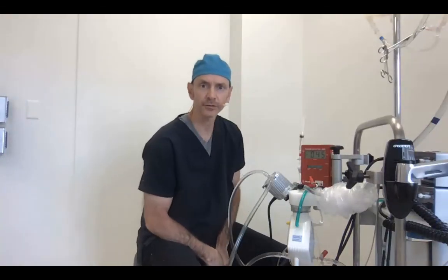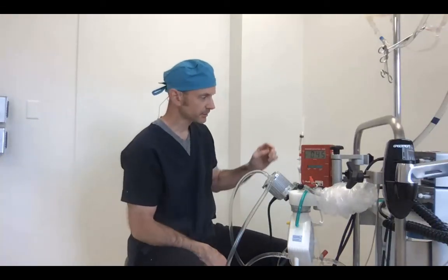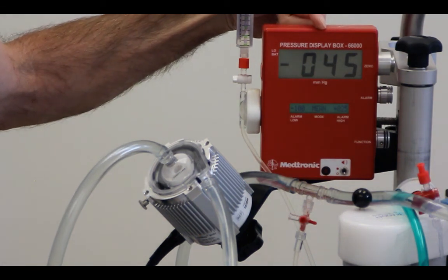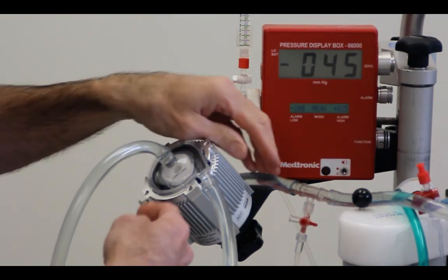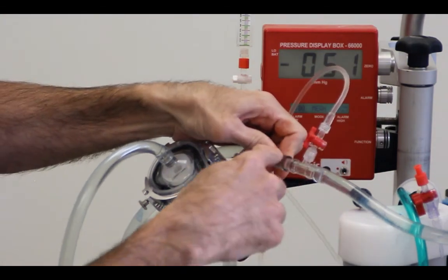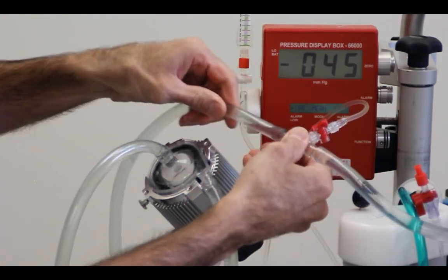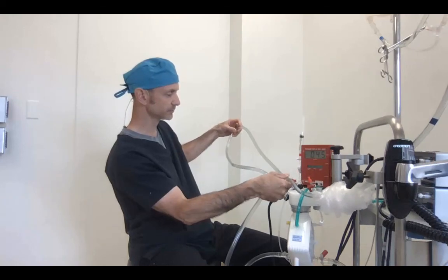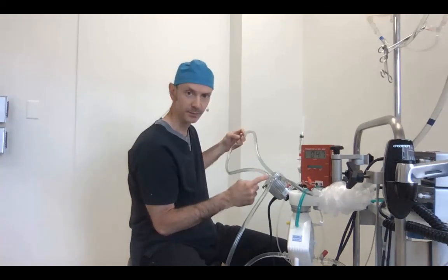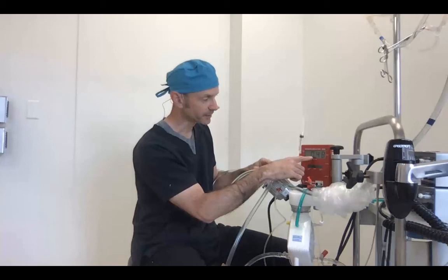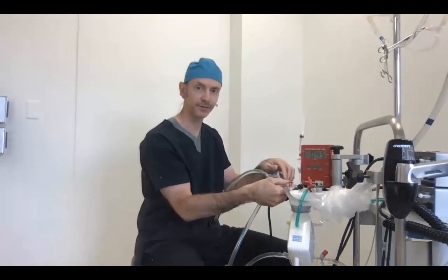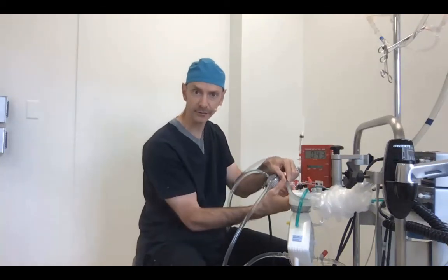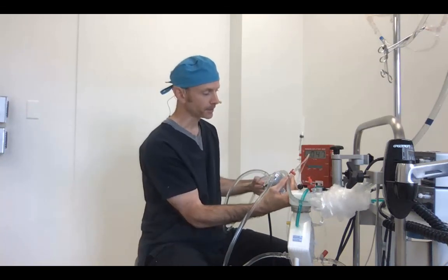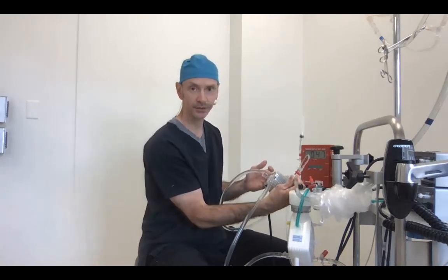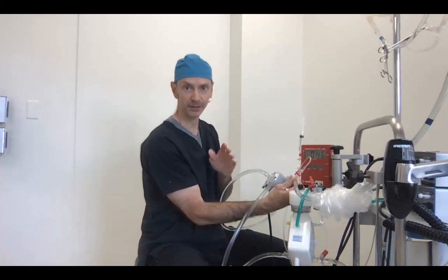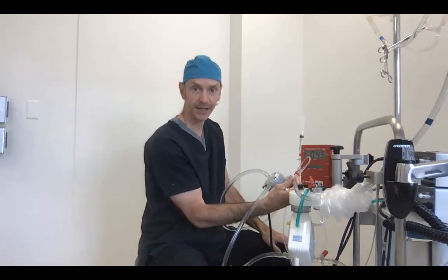Okay, so we moved a few things around now, and you can see your venous line pressure right here, and you can see the stopcock that is attached to the venous line right here, and then there's about 5 feet of tubing that goes to the inlet of this pump. Currently, we're measuring a venous line pressure of minus 48, which is very reasonable pressure. We're very happy with that if we're on ECMO with a minus 48. Sometimes it can be as low as minus 100. We say the normal range is minus 50 to minus 100, and I've certainly seen it lower than that, minus 125.